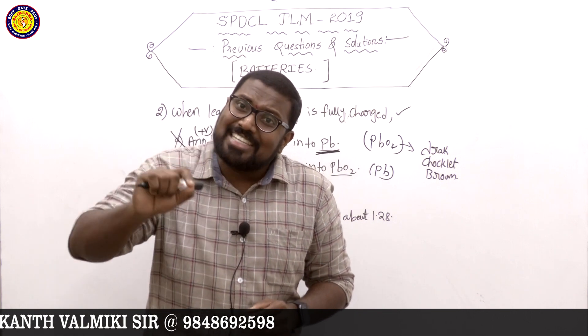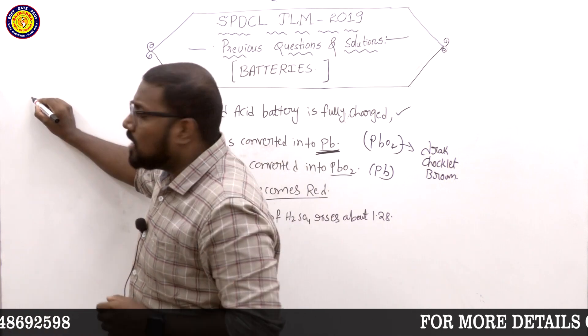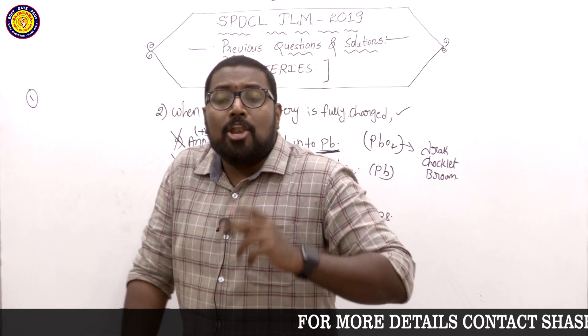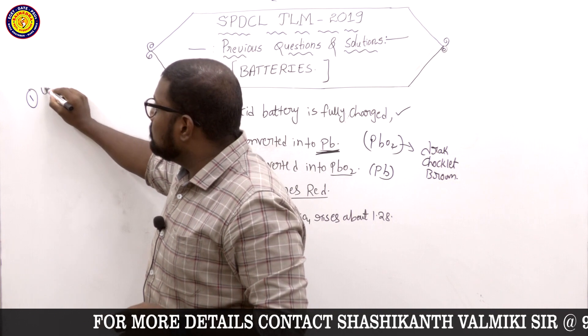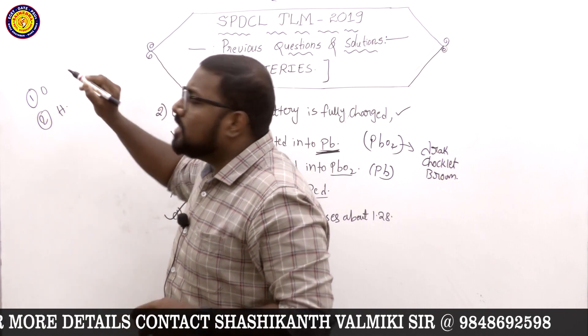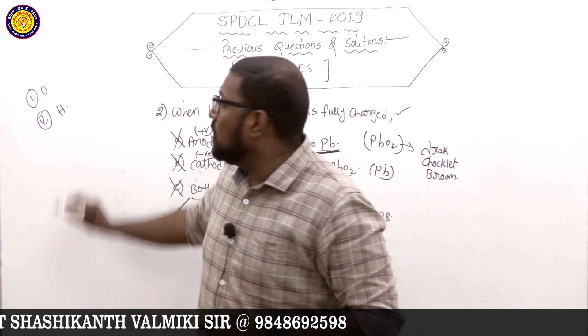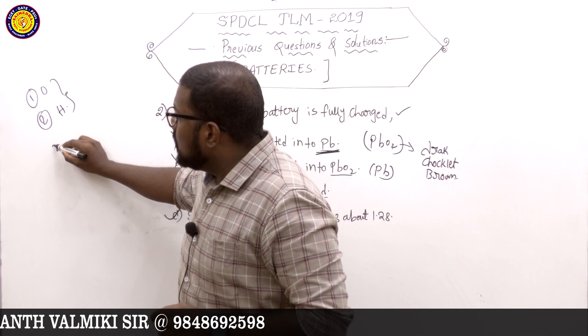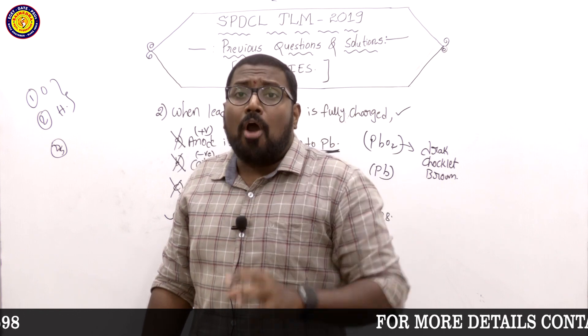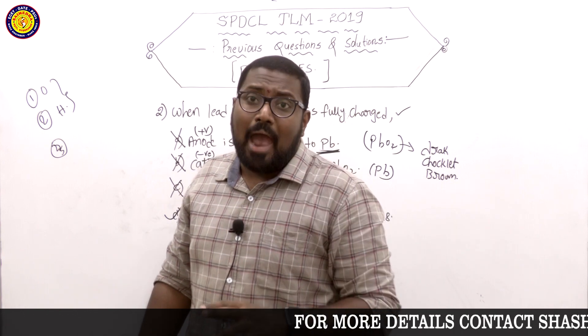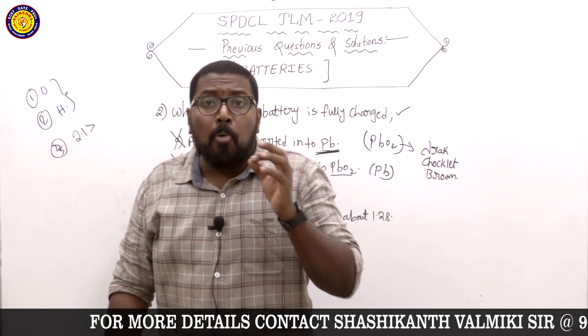The general symptoms of a fully charged battery are: at the anode, oxygen is liberated; at the cathode, hydrogen is liberated — this is called gassing. The EMF of the battery reaches 2.1 volts. These are the key conditions indicating a fully charged lead-acid battery.